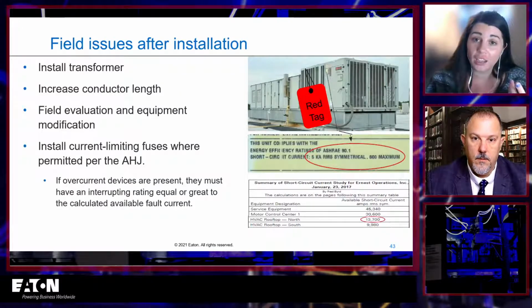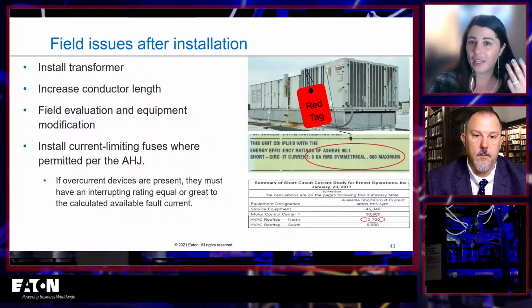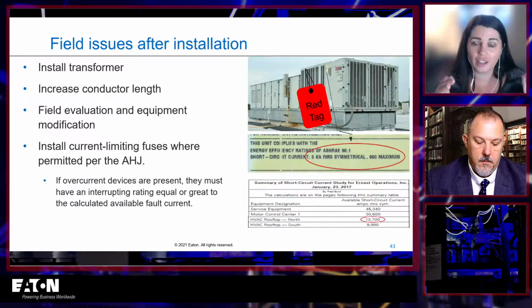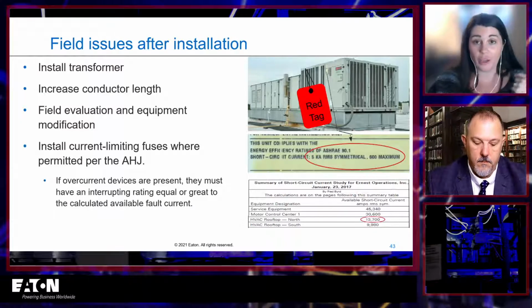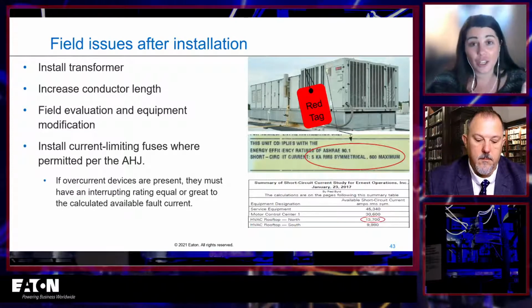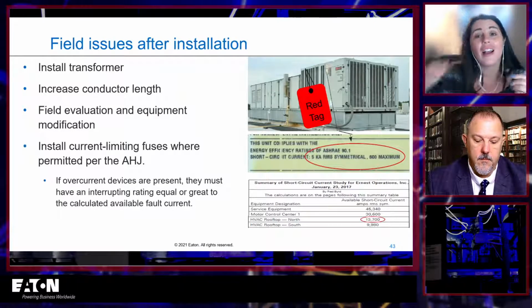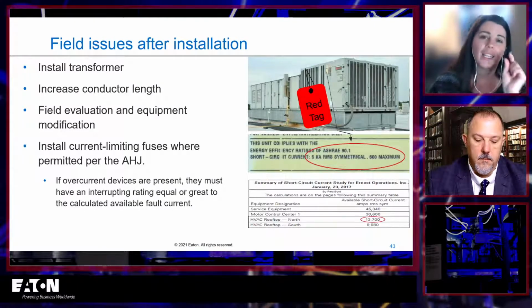You can increase your conductor length. This only makes sense in a couple situations, right? You have to be pretty close, right? Increasing your conductor length, you're not going to just add 500 feet extra of copper wire on top of your rooftop when your rooftop HVAC unit doesn't work, right? And you may as well install a transformer at that point if you do that. This makes sense if you're really close.